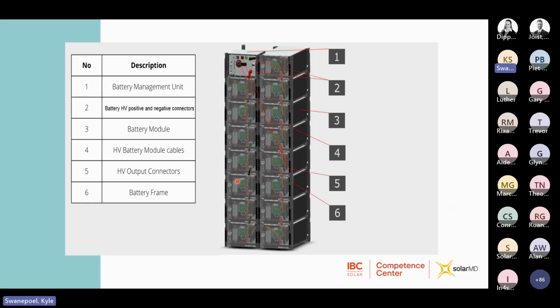All right. Just a quick overview of what we're looking at here. As I mentioned, the BMU, which is the battery management unit, is where your control sits for the battery. The communication sits here. You've got mechanical isolation, and then the connection points from the battery, as well as the output connectors that go to your inverter or DC bus. Then the battery positive and negative connectors over here on the right side. So that's connecting all of the battery modules in series to the BMU.